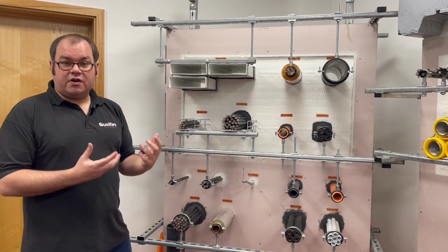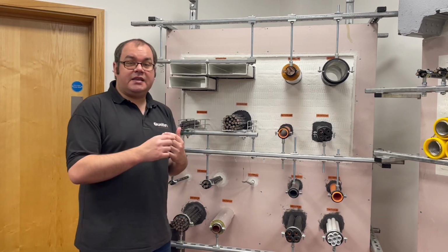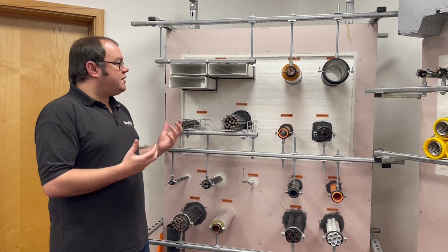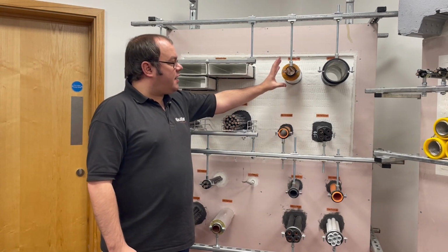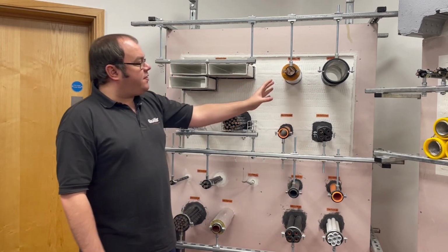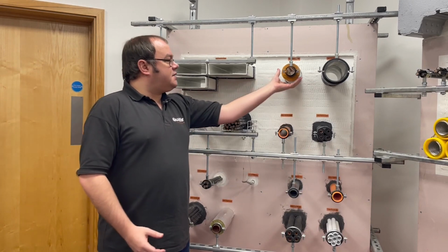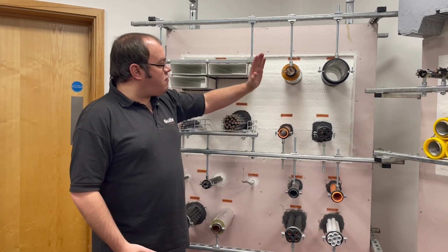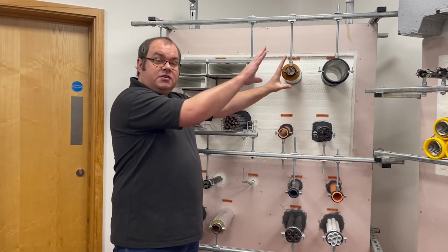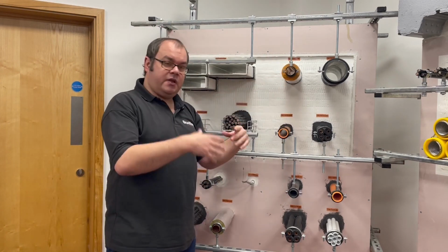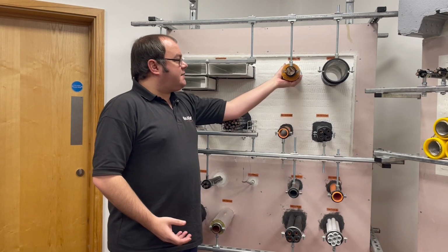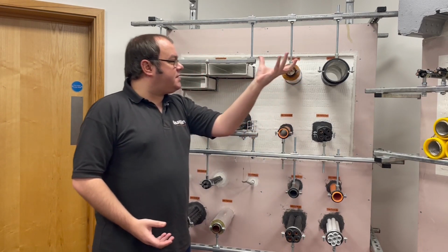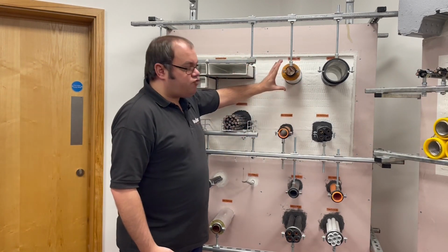So we'll look at the very first one, and that usually will be the letters C and S, and that stands for continuous sustained. So we take an example here. This is a metal pipe with phenolic insulation. When it says continuous sustained, this is describing the insulation going right through the penetration and then continuing on. So that's where you've got your insulated pipe works throughout a building.